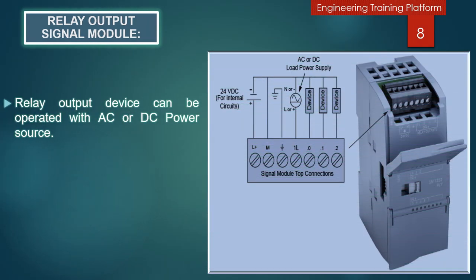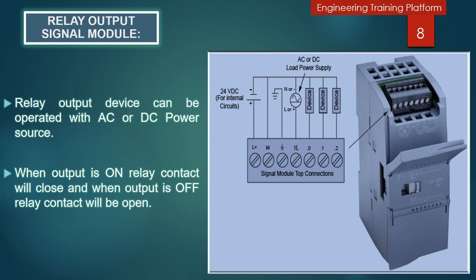Relay output signal modules offer the advantage of being able to work with either AC or DC devices, as long as the devices operate within the module's specifications and the switching speed required is not too fast. As shown in the picture, there is a set of relay contacts with eight relay output signal modules — three relay contacts above and five relay contacts below. When the output is on, the contact will close; when the output is off, the relay contact will be open.